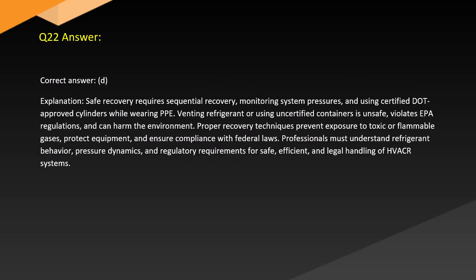Answer. Correct answer. D. Explanation. Safe recovery requires sequential recovery, monitoring system pressures, and using certified DOT-approved cylinders while wearing PPE. Venting refrigerant or using uncertified containers is unsafe, violates EPA regulations, and can harm the environment. Proper recovery techniques prevent exposure to toxic or flammable gases, protect equipment, and ensure compliance with federal laws. Professionals understand refrigerant behavior, pressure dynamics, and regulatory requirements for safe, efficient, and legal handling of HVACR systems.